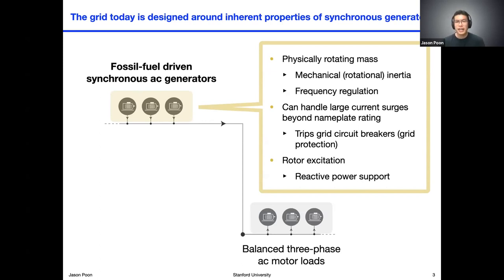Similarly, a large rotating generator provides a very natural means of doing frequency regulation — if the grid is drawing too much power, the frequency of rotation will slow from its rated speed, some multiple of 60 hertz in the United States. That slowing of the machine is a natural signal to the operator that more power needs to be introduced. Secondly, these generators can handle large surge currents beyond their nameplate rating — typically about 5 to 7x for very brief periods.